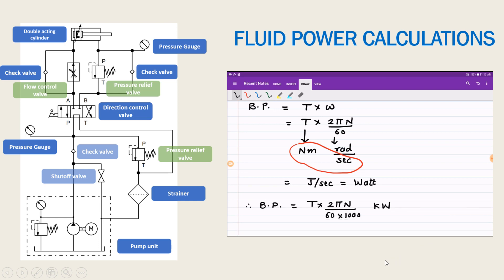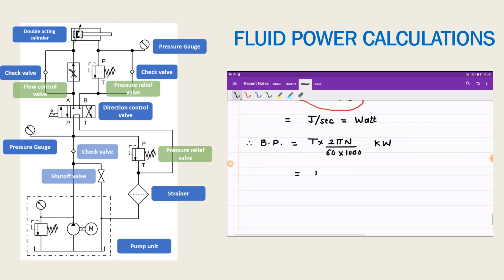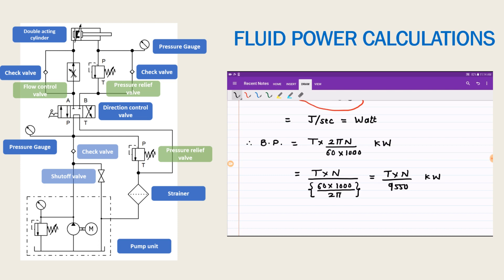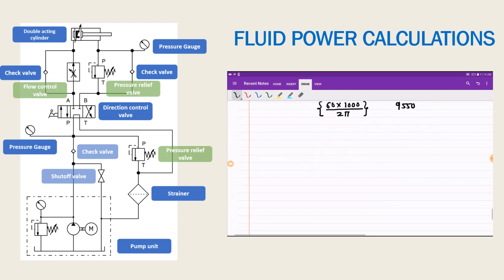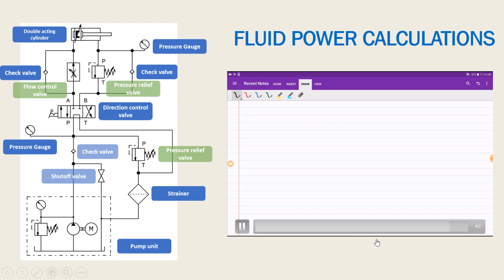To convert to kilowatt, divide by 1000, so brake power equals T times 2 pi n divided by 60,000. Rearranging, this equals T times n divided by 9550, since 60 times 1000 divided by 2 pi equals approximately 9550. This standard relation converts brake power to kilowatt using torque in Newton meter and speed in rpm.